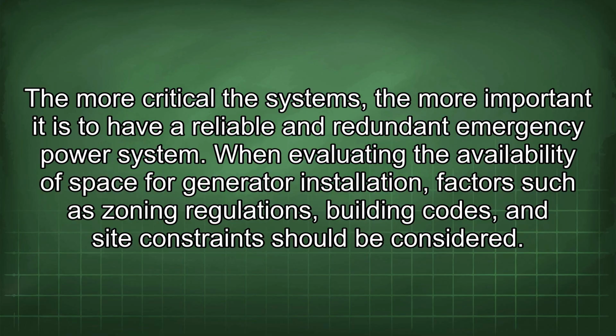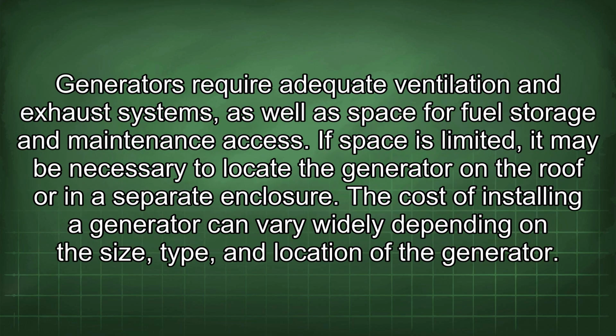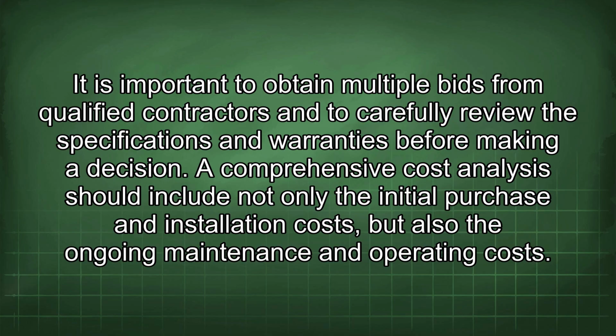When evaluating the availability of space for generator installation, factors such as zoning regulations, building codes, and site constraints should be considered. Generators require adequate ventilation and exhaust systems, as well as space for fuel storage and maintenance access. If space is limited, it may be necessary to locate the generator on the roof or in a separate enclosure. The cost of installing a generator can vary widely depending on the size, type, and location of the generator. It is important to obtain multiple bids from qualified contractors and to carefully review the specifications and warranties before making a decision. A comprehensive cost analysis should include not only the initial purchase and installation costs, but also the ongoing maintenance and operating costs.